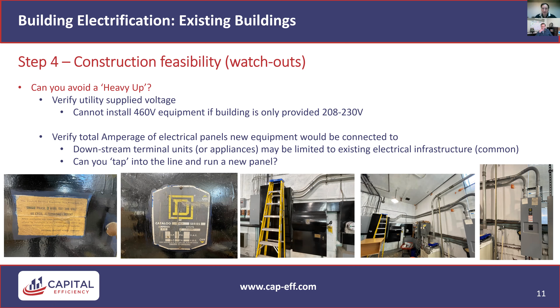These pictures represent what that may look like. Moving left to right, you can see the building is provided 120 and 208 volts, and the total amperage from the main panel is 600 amps. What was done, as you see at the top, is a tap-in line basically bypassed this panel and ran all the way around to a separate panel so that the additional amperage, in this case for rooftop units, could be supported. So don't assume electrifying an existing building automatically means a heavy-up, because there may be space and safety constraints. If it's possible, you might be able to do some workarounds - of course, consult an electrical engineer.